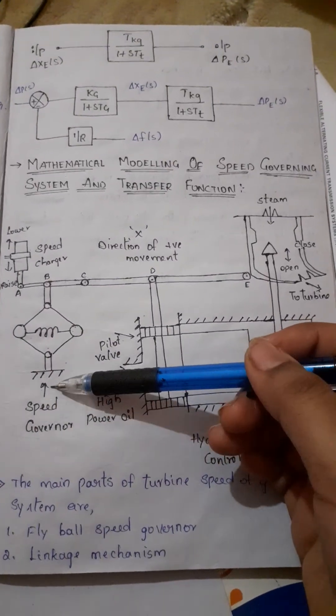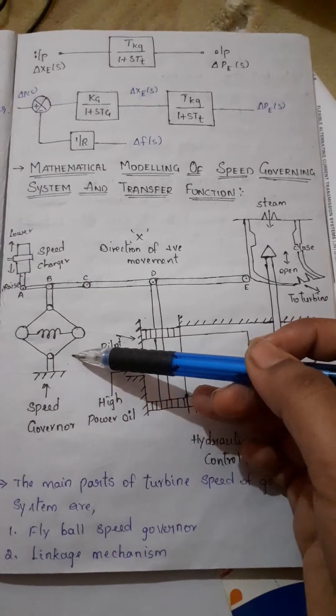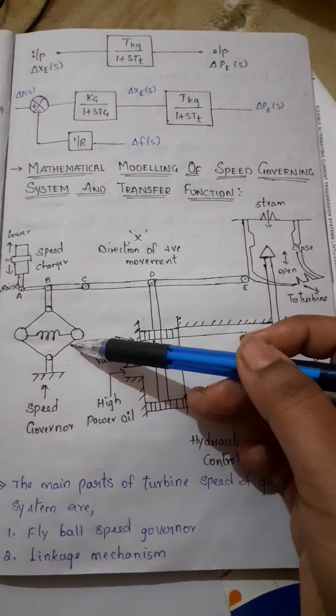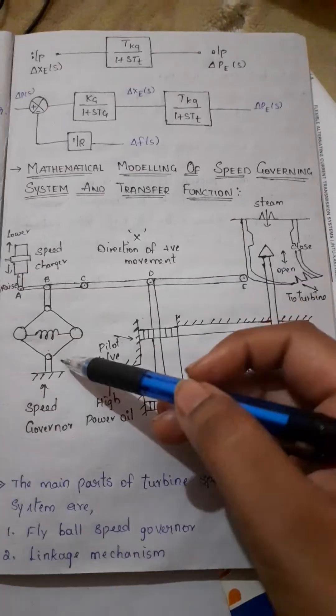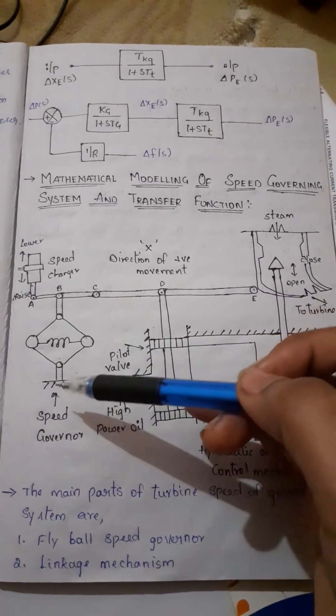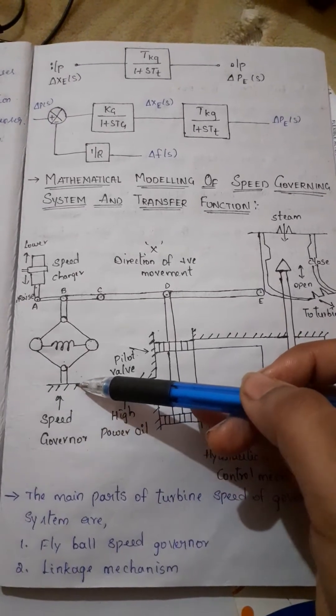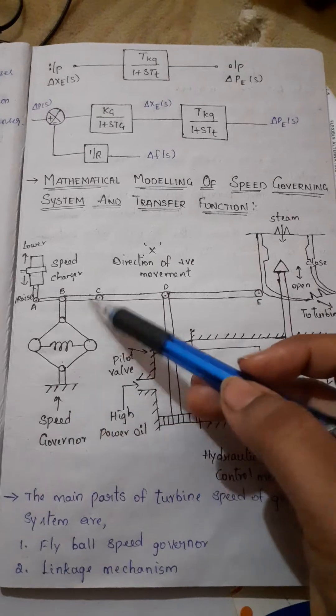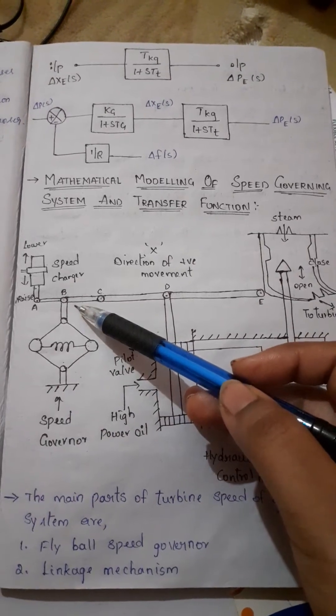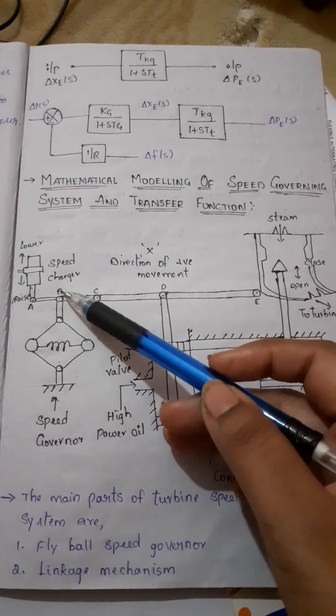The speed governor is the heart of the system and it senses the change in speed. The speed governor senses the speed. Whenever there is a change in speed, it senses it. As the speed increases, the fly ball moves outward and this point on the linkage mechanism moves downwards.